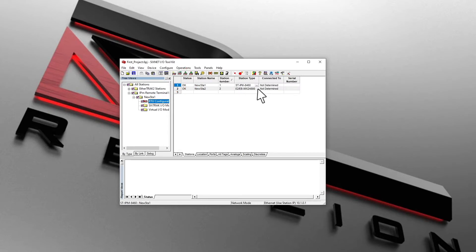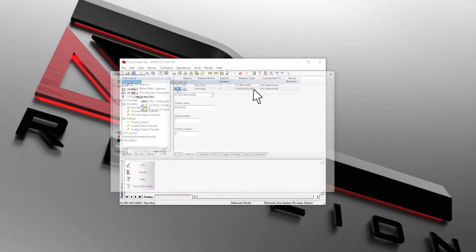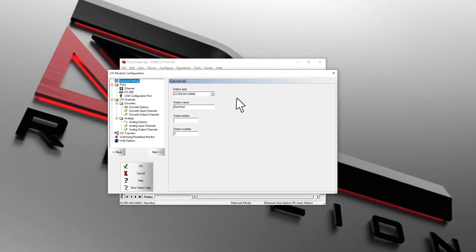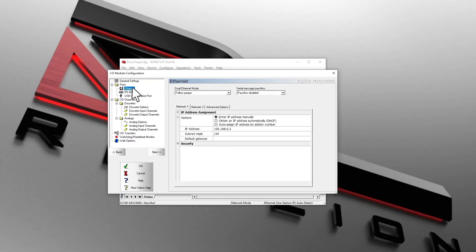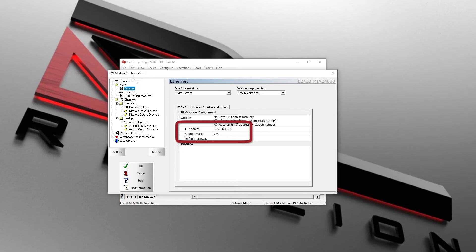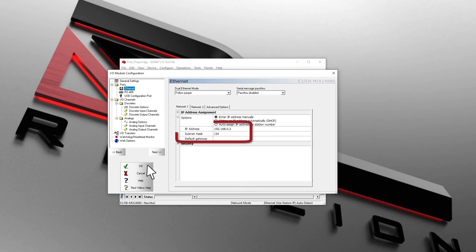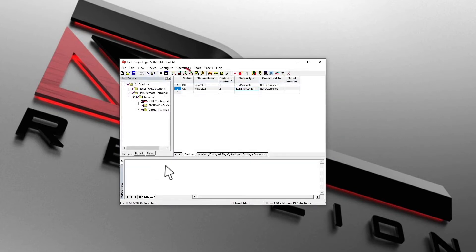Now, we'll configure the EtherTRAK-2 by clicking on the Dialog button. Click on Ethernet in the Tree Views window to configure the IP address. Notice that the IP address we have selected here is 192.168.0.2. Set the subnet mask to Class C, which is compatible with Interface 2 on the RTU. The fourth digit in the IP address, by default, matches the slave address, which is 2. Load this configuration by clicking the Load button on the toolbar.